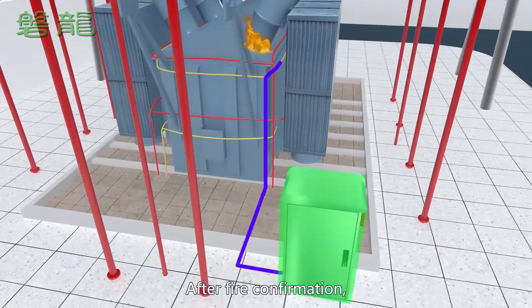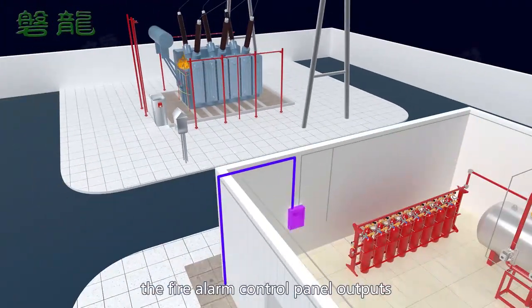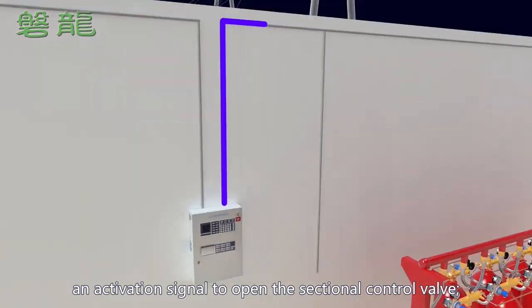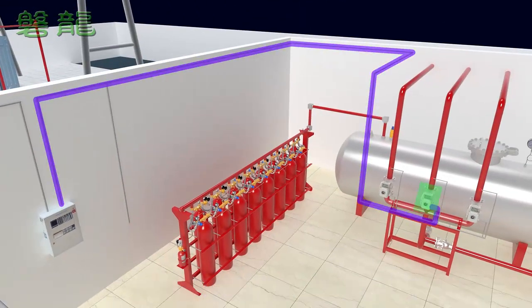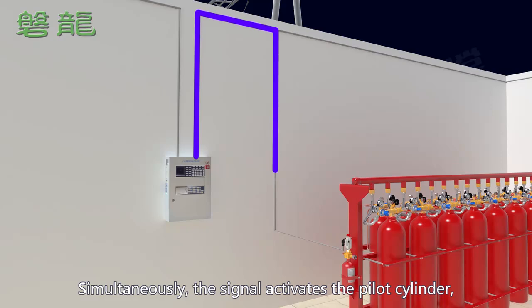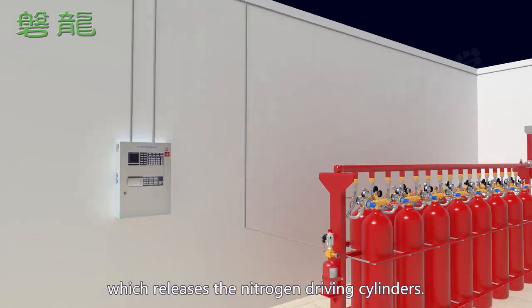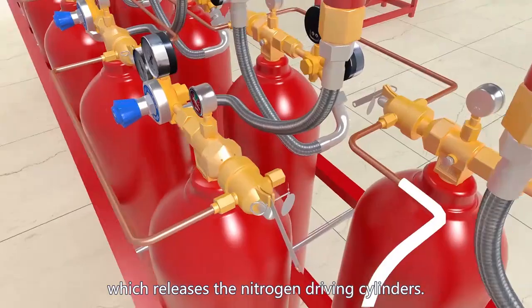After fire confirmation, the fire alarm control panel outputs an activation signal to open the sectional control valve. Simultaneously, the signal activates the pilot cylinder, which releases the nitrogen driving cylinders.